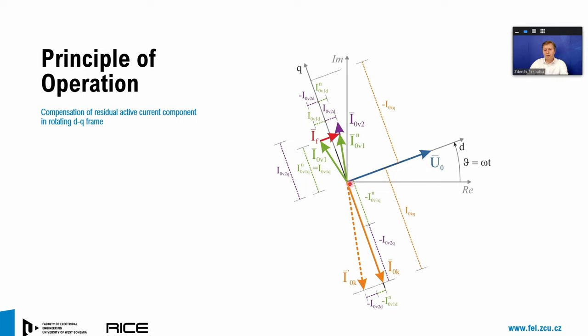What we can see on the next slide is that if we operate only the arc suppression coil, the arc suppression coil, depending on the zero sequence voltage, is able to generate the inductive current, which acts against the fault current, which is in this quadrant. In our case, we are able to shift and adjust the compensation current, and we are able to fully compensate the fault current, including its active component as well as high harmonics, which is very important.